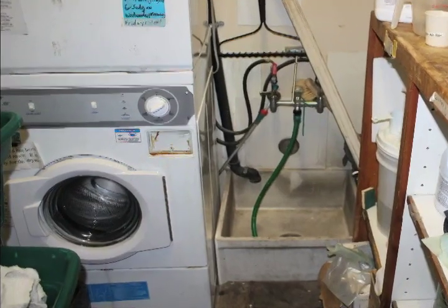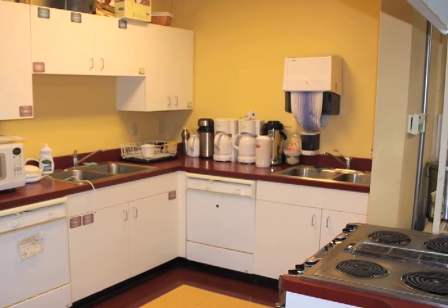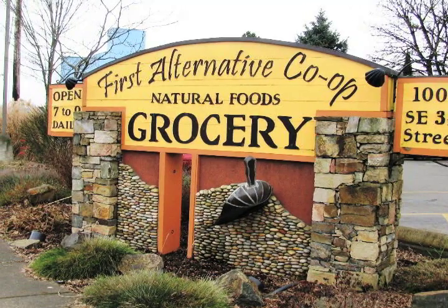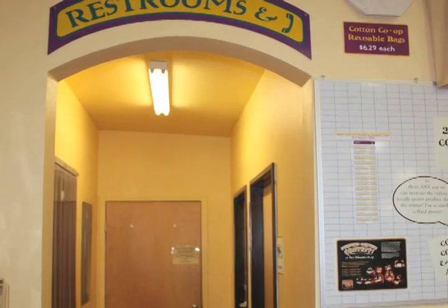Oregon identifies graywater as any water produced from washing machines, kitchen sinks, or showers. Oregon recently passed legislation which allows the recycle of graywater within a home or business. For our project, we had to file 2 separate plumbing permits, one for the rainwater tank and the other for our filter. For the scope of our project, we decided on using hand washing sinks from the 2 public bathrooms and rainwater to recycle into the 2 public toilets here on site.